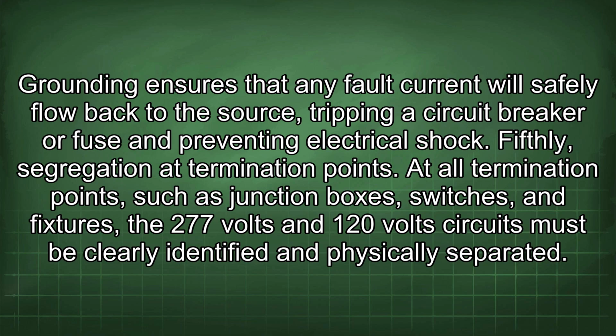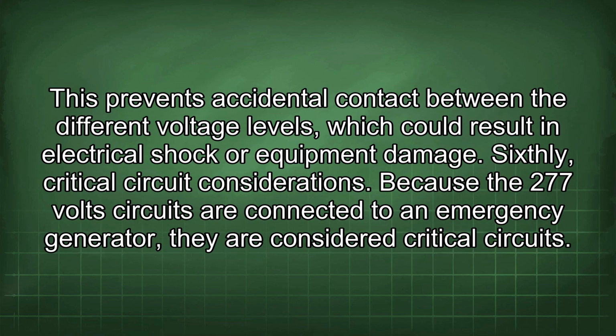Fifthly, segregation at termination points. At all termination points, such as junction boxes, switches, and fixtures, the 277 volt and 120 volt circuits must be clearly identified and physically separated. This prevents accidental contact between the different voltage levels, which could result in electrical shock or equipment damage.